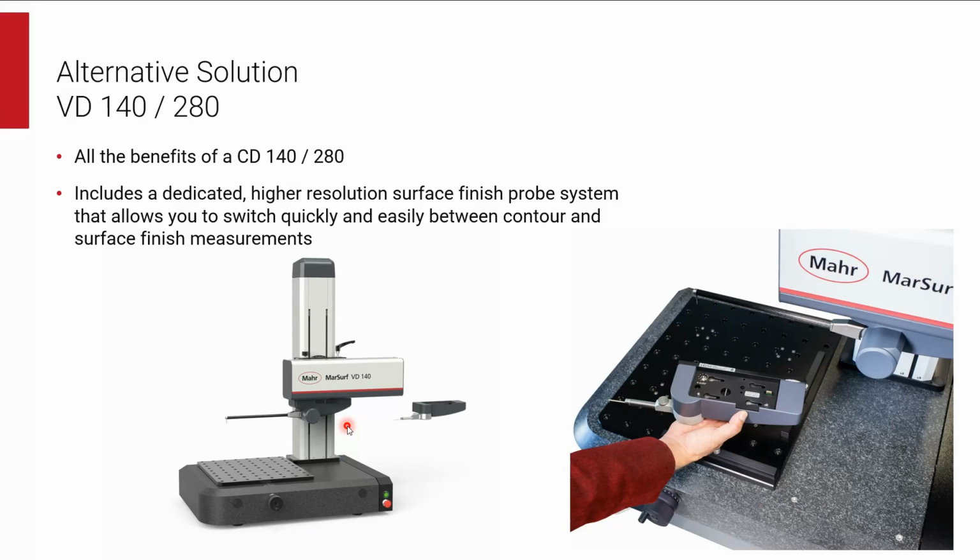And again, you can swap them as many times as you want without having to perform any recalibration of the machine or of any probes that we use with the probe system.